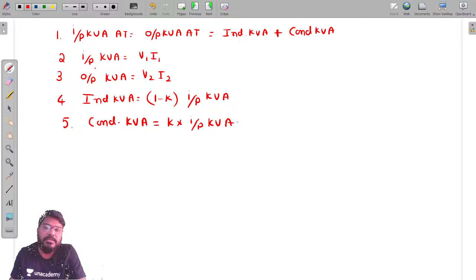How do we get conduction kVA? K times of the input kVA of auto transformer. Or otherwise we can also get the input kVA of auto transformer minus induction kVA or output kVA of auto transformer, or otherwise output kVA of auto transformer minus the induction kVA of auto transformer.